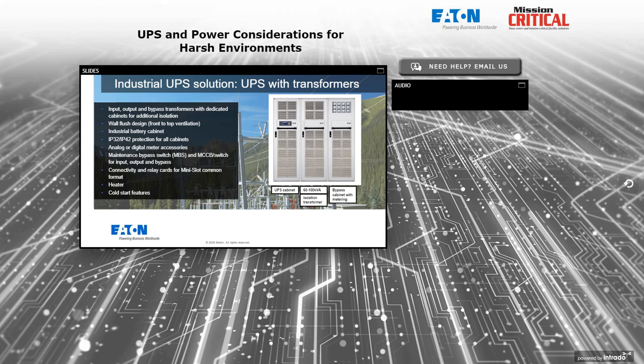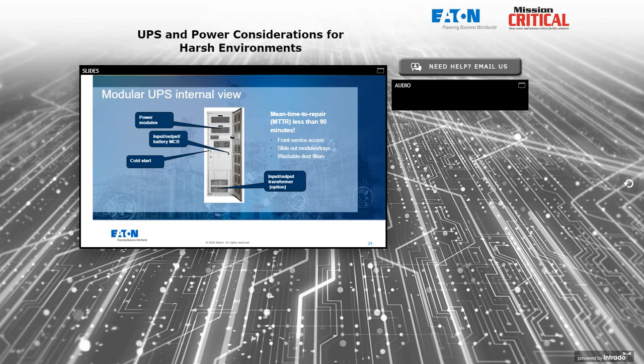Maintenance bypass switches, either external or wall-mounted beside the UPS, always recommended. And connectivity and relay cards for communication that can be certified to be high cybersecurity and hacker-resistant type communications. Some clients in cold environments, of course, require an internal heater be mounted inside the UPS or inside the battery cabinet. And then that cold start feature where I can start the machine from the battery cabinet is another place where that gets used.